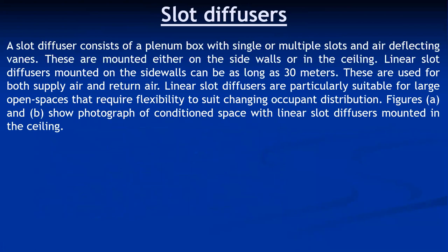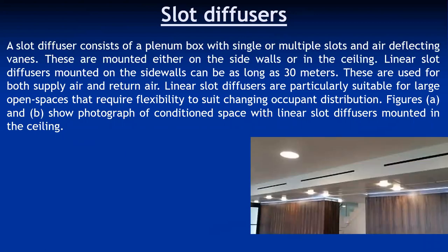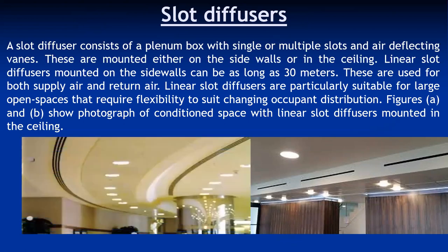The third type is slot diffusers. A slot diffuser consists of a plenum box with single or multiple slots and air-deflecting vanes, mounted either on the side walls or in the ceiling. Linear slot diffusers mounted on the side wall can be as long as 30 meters, and are used for both supply and return air. They are particularly suitable for large open spaces that require flexibility to suit changing occupant distribution, and are commonly used in offices, passages, and lobbies.